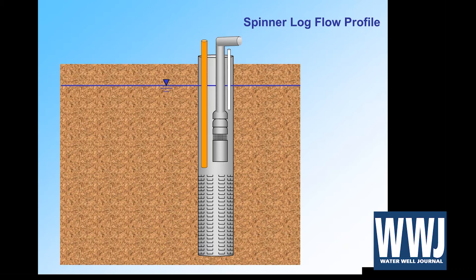I'm showing a submersible pump here — it could be a vertical turbine pump, but a submersible is a little easier. We have the motor intake and our pump bowls, and above it a sounding tube where we can measure water levels just like normal. There's also an access tube, usually about three inches in diameter, open at the bottom. This allows us to run wireline tools down past the pump while it's running and then evaluate our screened interval.